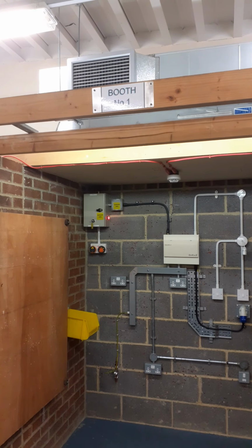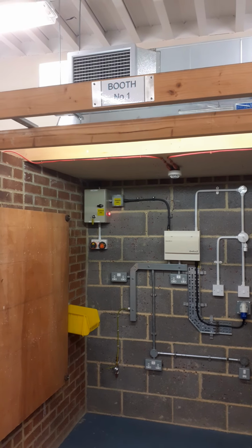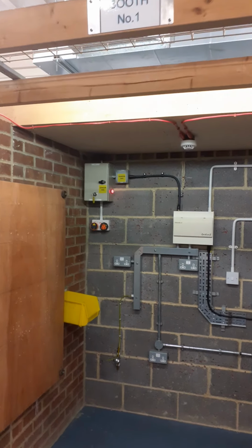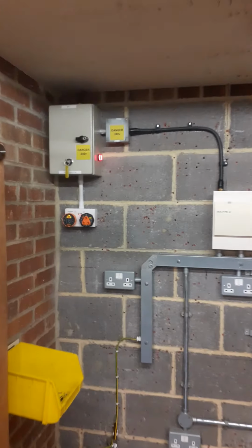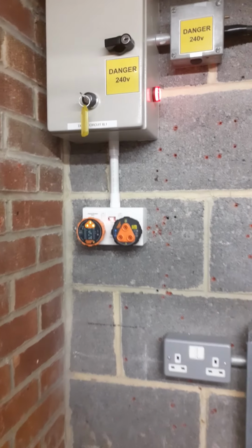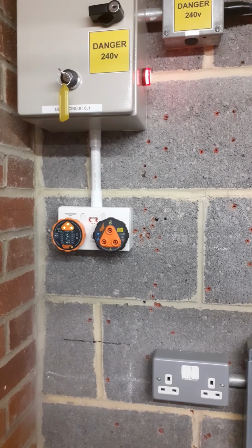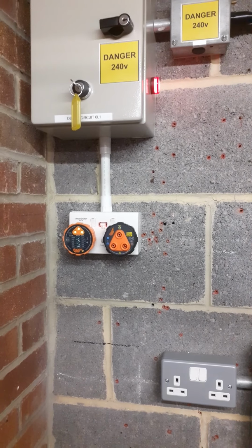Hi, what we're going to do, we're going to safely isolate booth 1. As you can see, the red indicator light's on in the bay. The live plug socket tester is illuminated and it's buzzing, and we'll have a dead plug socket tester plugged in. To kill the power supply to the bay, what we do is we hit the emergency stop.